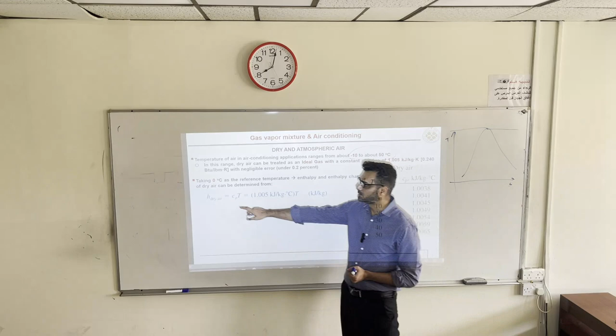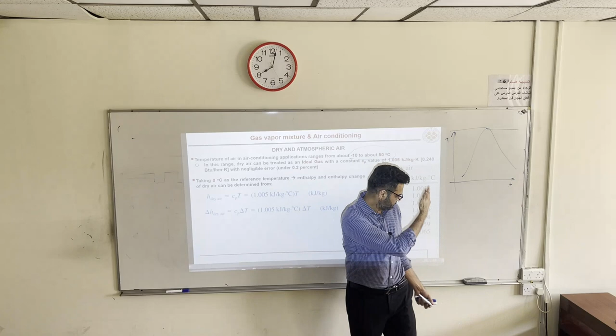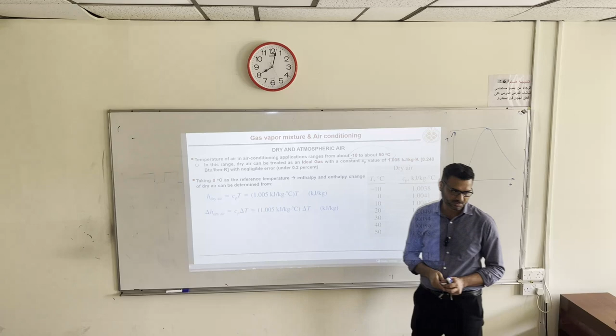Now in this range, the air properties which we need in the calculation of air conditioning, the Cp value can be assumed constant. There is no worry of using variable specific heat of air. This changes in the third decimal, and that is negligible. Okay, that's what we are trying to say. Okay, so you can calculate enthalpy of dry air using that equation at any temperature for the change in temperature, Cp into delta T. So you are using that averaged Cp, this averaged Cp multiplied by whatever is the temperature change to calculate the enthalpy change. Okay.